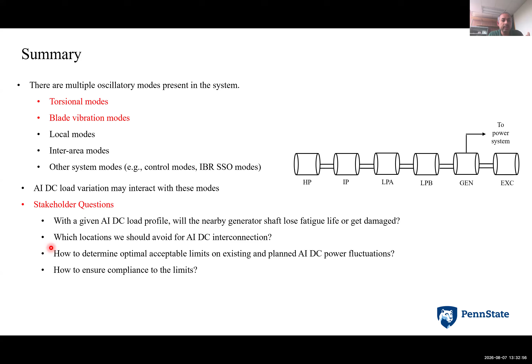The other side of the spectrum is, if I have an interconnection queue and certain AI data center projects, which are the buses or locations I would definitely want to avoid to make sure we have mitigating measures that will be feasible. And if I have multiple such AI data center loads in the system, how do I optimally determine the limits on the AI data center fluctuations? Finally, how do we check compliance?